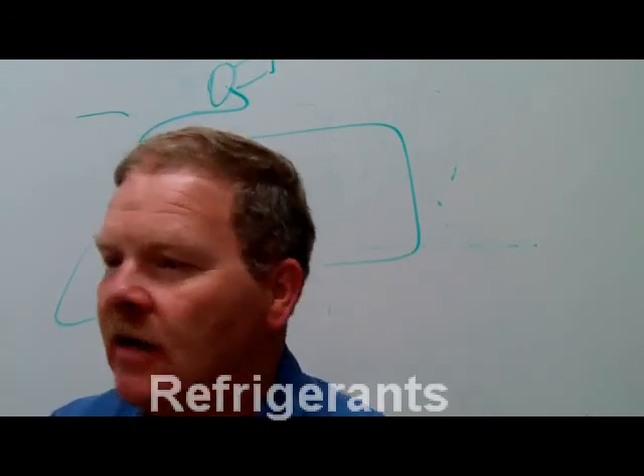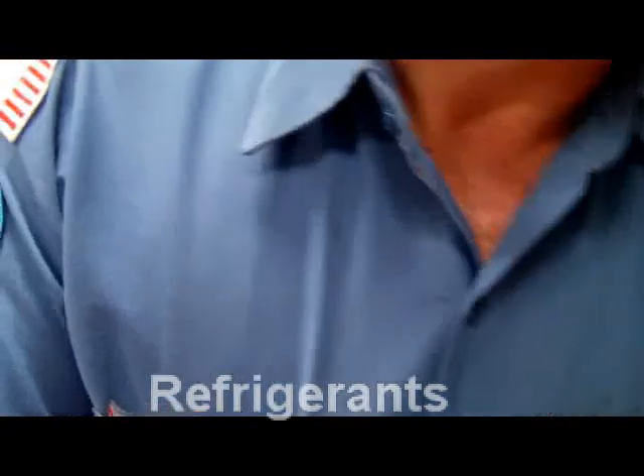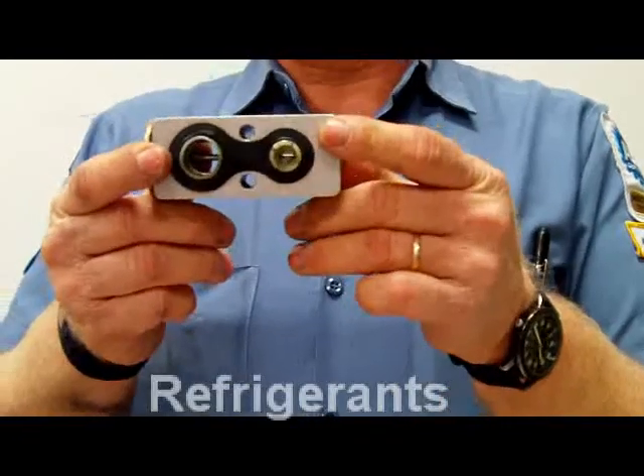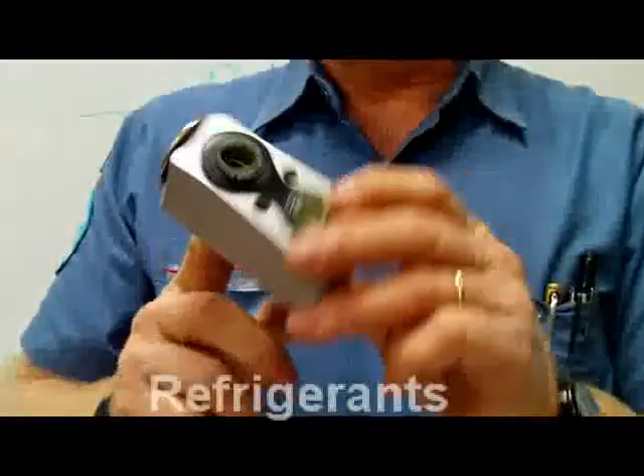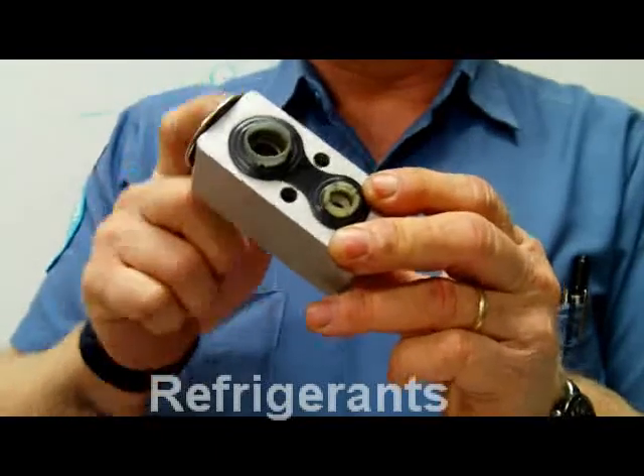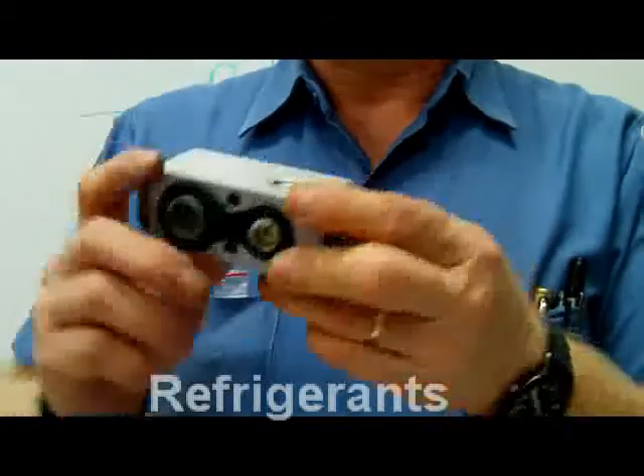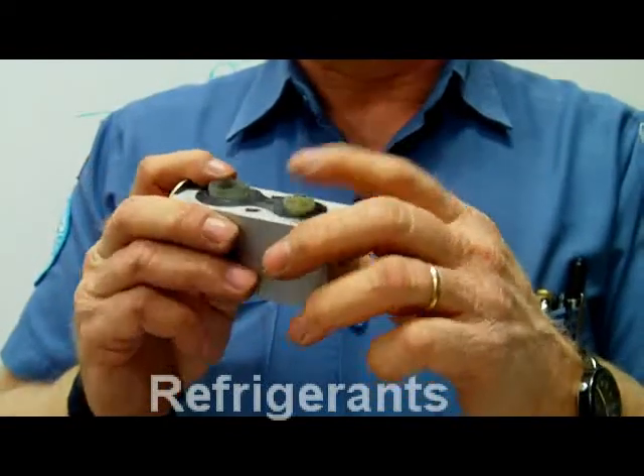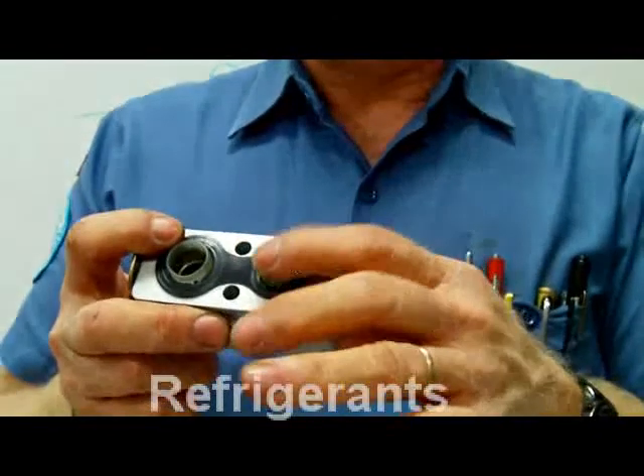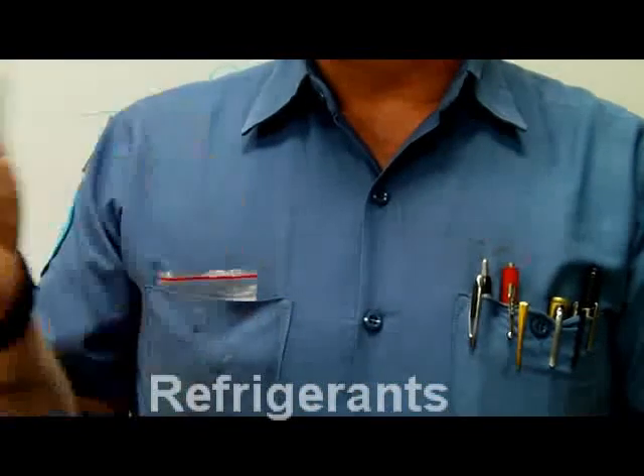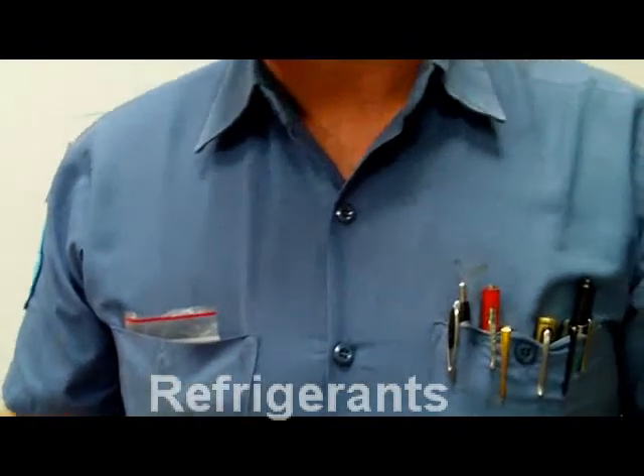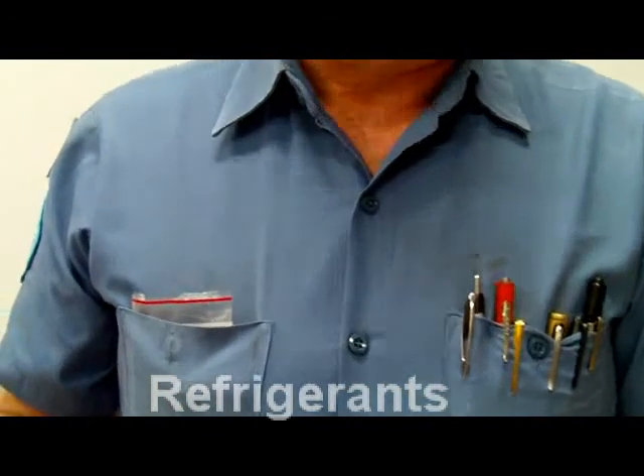So you're supposed to be recognizing the fact that if you have an expansion valve, you're going to have a dryer in the liquid line. Remember that? Have you ever seen an expansion valve? Do you guys know what it looks like? That is one type of expansion valve. The low side is here. The high side is here. As this goes through there, the temperature causes this alcohol chamber to actually change the size of that orifice. That's why they call the other one a fixed orifice. It's actually going to change the amount of refrigerant that can go through here. And mostly what they're trying to prevent is they're keeping the evaporator from icing up. Because if the evaporator ices up, you're not doing anybody any good because no air can flow through an iced-up evaporator, right?